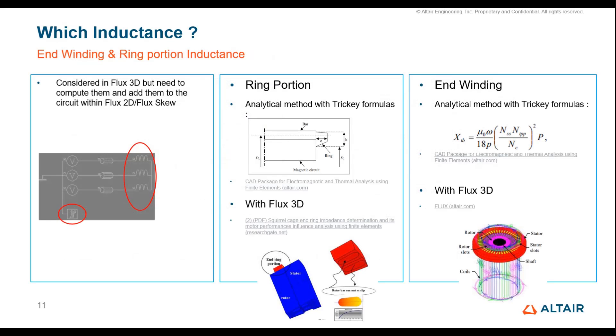In 2D there are other inductances to consider, mainly end winding inductances. For an induction machine there is ring portion impedance, and for the ring portion inductance there are some formulas — the Trickey formula — which can be found in our tutorial for a skewed rotor example. It is also possible to determine it in Flux 3D; we published an article where we computed the impedance of the end ring portion using Flux 3D. For the end winding inductance, this formula is mainly what we use in Flux Motor, and there is also a possibility to compute it with Flux 3D with an available tutorial.